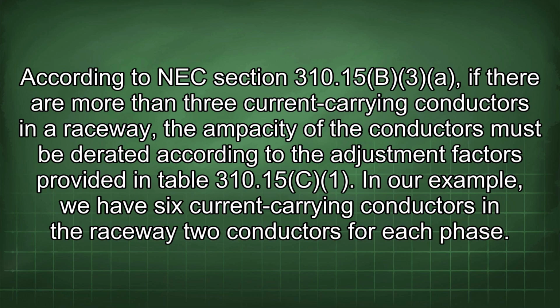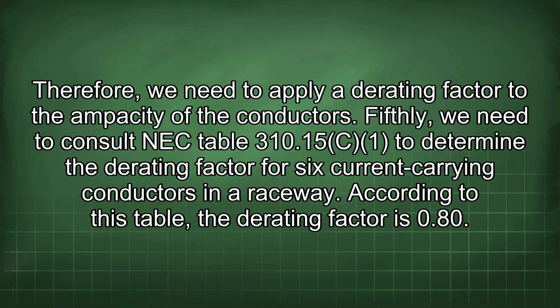According to NEC Section 310.15(B)(3)(a), if there are more than 3 current carrying conductors in a raceway, the ampacity of the conductors must be derated according to the adjustment factors provided in Table 310.15(B)(3)(a). In our example, we have 6 current carrying conductors in the raceway, 2 conductors for each phase. Therefore, we need to apply a derating factor to the ampacity of the conductors.